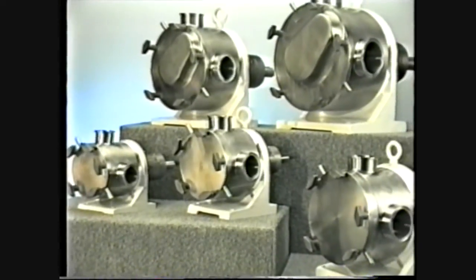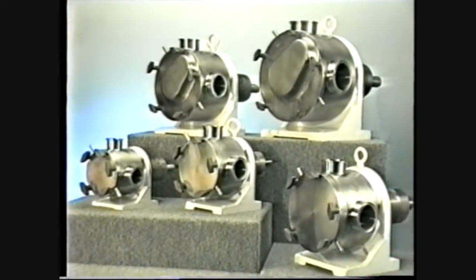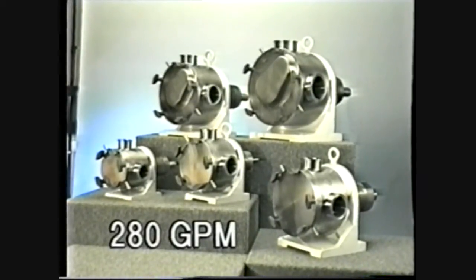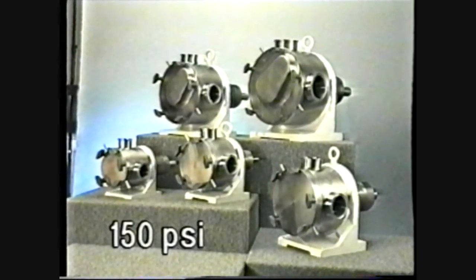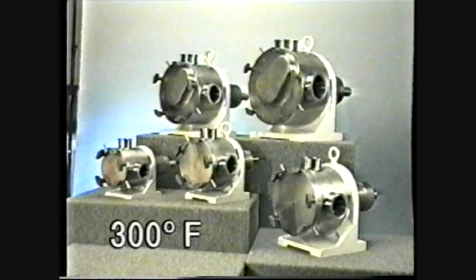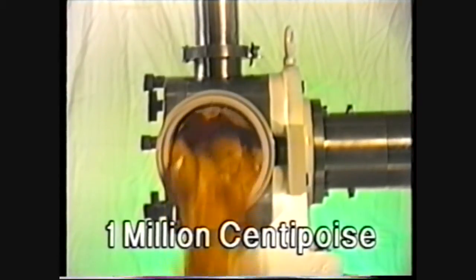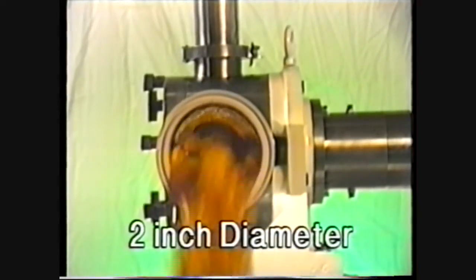The complete Sine Pump product line shown here is capable of flows to 280 gallons per minute, pressures to 150 psi, temperatures to 300 degrees Fahrenheit, product viscosities to 1 million centipoise, and particle sizes to 2 inches in diameter.